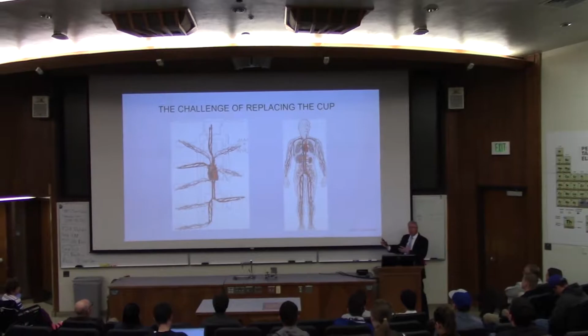Challenges. We ultimately had to map digitally, provide a 3D digital map of all the utilities that were in the area. We had to keep the plant operating, and it was similar to trying to do open heart surgery. When you do open heart surgery, you've got to keep the body still functioning. You've got to have the blood flowing. Well, we had to have chilled water and hot water still flowing in our central terminal area, while we were building something new and building all the cutovers as the new plant was ready to be commissioned. It was quite a logistical and coordination challenge to keep that operating.